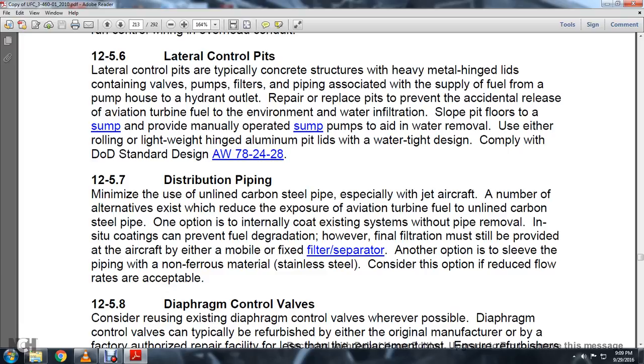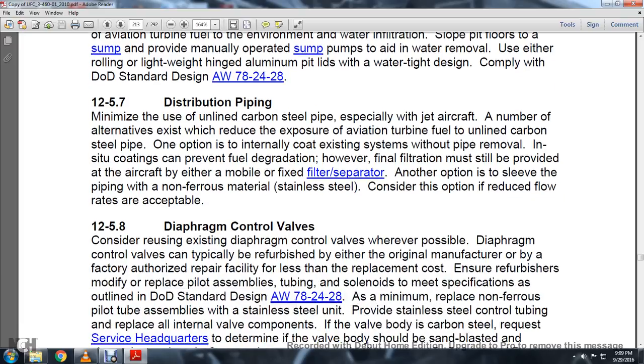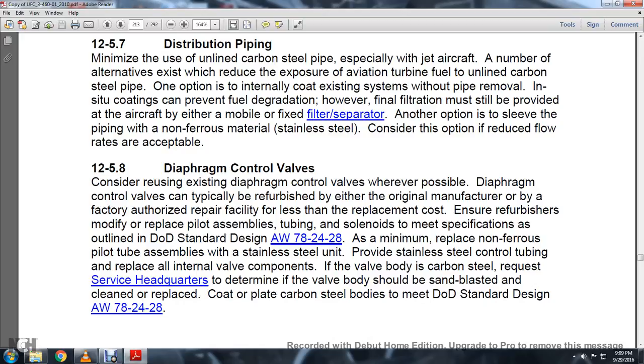Another option is to provide piping of non-ferrous material such as stainless steel. Consider this option to reduce flow restriction and ensure acceptability. Section 12-5-8: Diaphragm control valves. Where possible, refurbish diaphragm control valves through the original manufacturer or factory-authorized repair facility for less than replacement cost. Ensure the refurbisher modifies or replaces the pilot assembly tubing and solenoids to meet the specifications outlined in Department of Defense AW78-2428. Minimum replacement requirements include non-ferrous pilot tube assembly and stainless steel control tubing. Components of carbon steel valve bodies should be sandblasted and cleaned, and carbon steel bodies recoated.